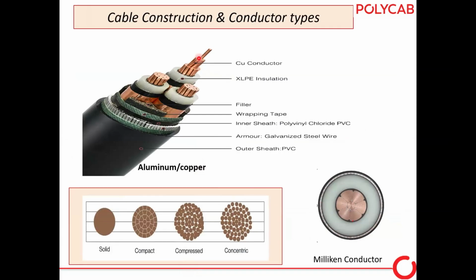Copper conductor is there, or might be aluminum conductor, then the semiconducting layer, that's black in color. Then over that, XLPE insulation, and again a semiconducting layer. Then three cores are bunched together. Fillers are there to give the round shape. Then we wrap it; the wrapping tapes are there. Then armour is there, and then the outer sheath. So this is the basic construction of the cables.